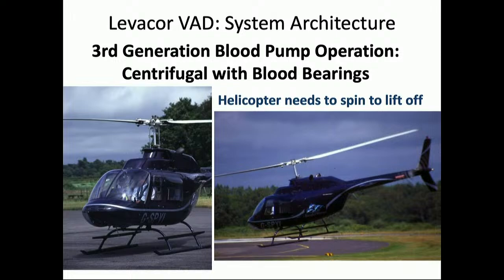The third generation pumps were the hydrodynamic pumps. I'm using kind of technical language, but basically using blood as a suspension mechanism like a helicopter does. The helicopter has to spin its wings to lift off. So they were using the hydrodynamic properties of blood as a suspension medium to lift their impeller off. For example, there's a device called the Heartware HVAD that was recently withdrawn from the market that depended on this principle. It didn't have mechanical ball bearings, but it depended on this helicopter effect to have the spinning part floating in blood. But as you well know, someone alluded to the great variation in patients, right?